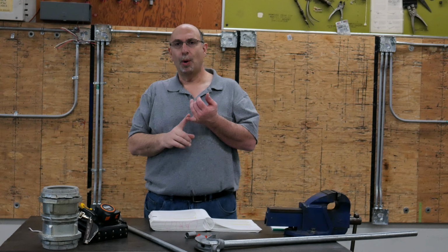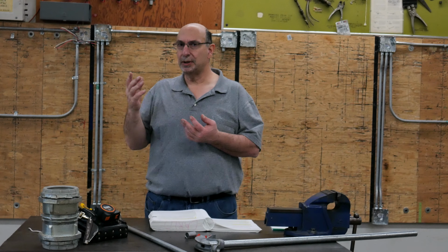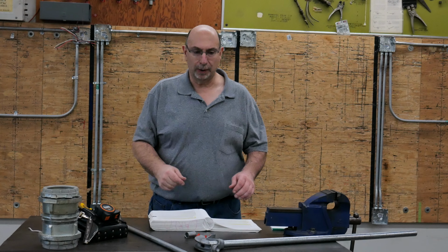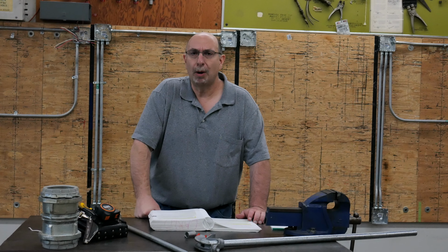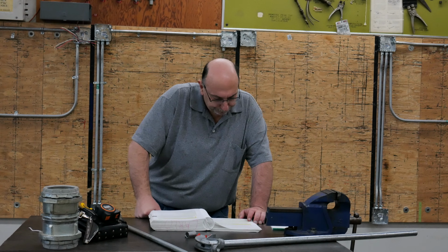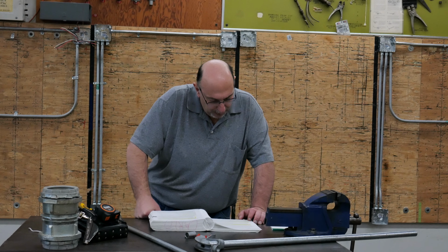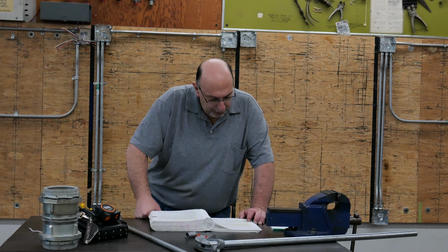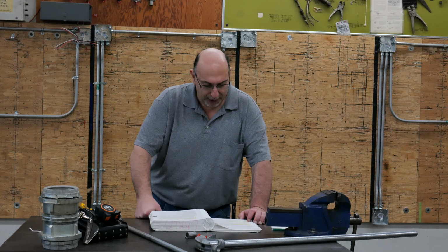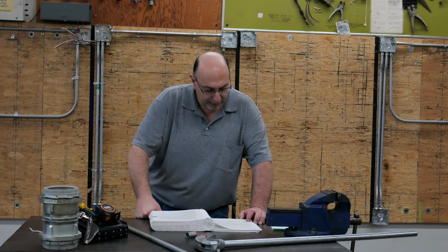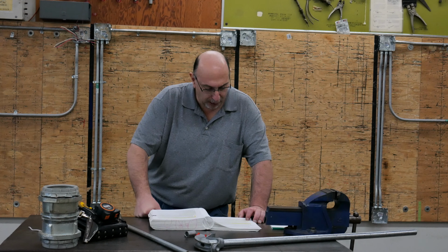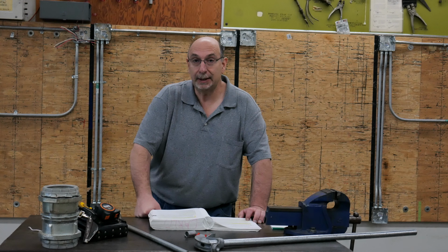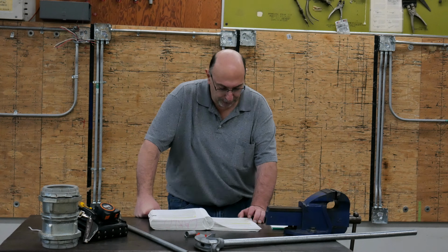No oils, no greases, no lubricants, just whatever you purchase from the wholesaler. Usually it's poly water or yellow 77. All right, subrule 2. Lubricants used when inserting insulated conductors in raceways shall be either insulated conductor pulling compound, talc, or soapstone. So that's the only types that you're allowed to use.